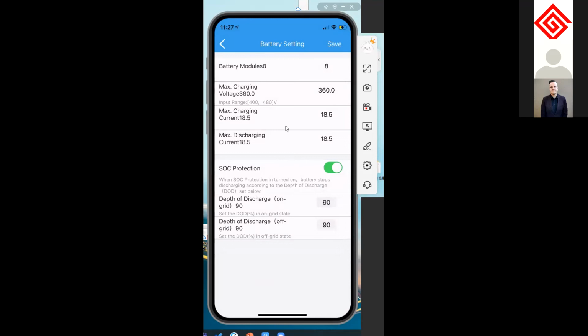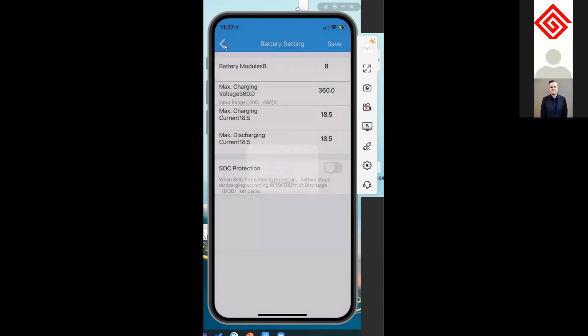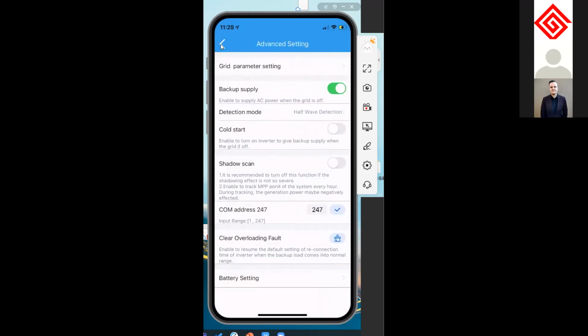On the bottom side here, you have battery settings. And here you see that this is all gathered automatically from the BMS. In case you have lead acid batteries, then you might need to set this manually. Here you can activate or deactivate this one to have a customized state of charge protection and change the depth of discharge manually. We just turn it off now. When you're done, you just press save. It's saved, and then you can go back to the other menu. Let's go back one more.